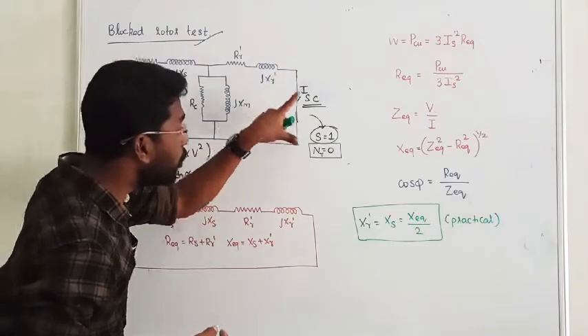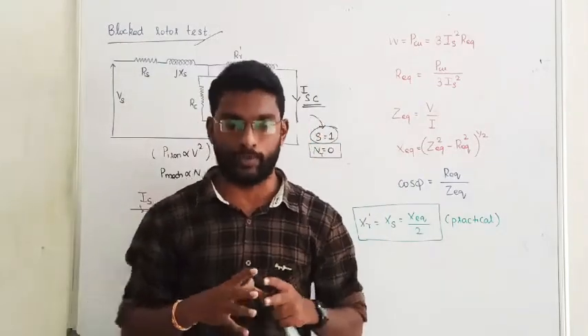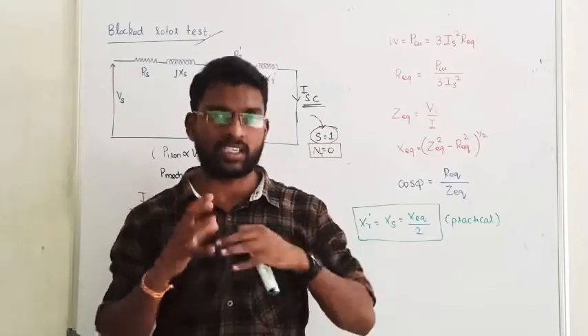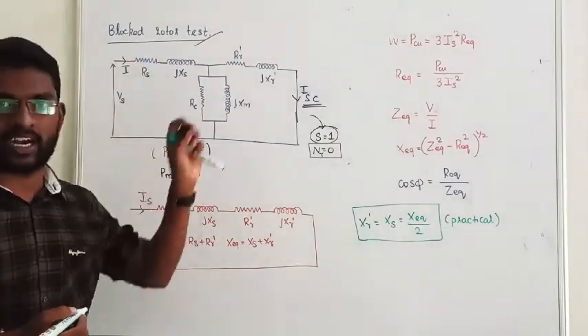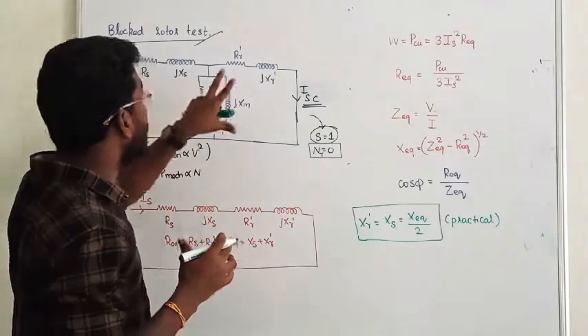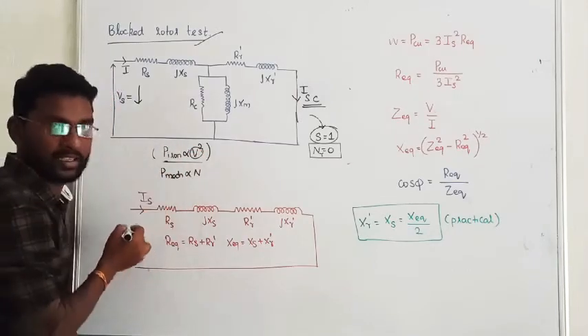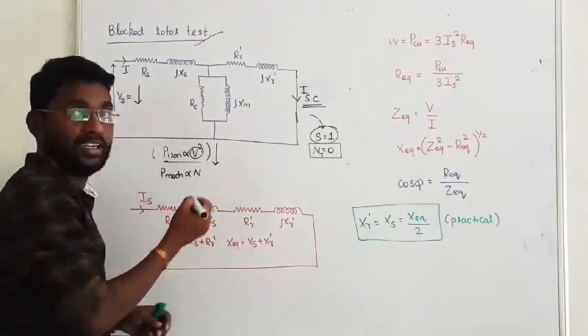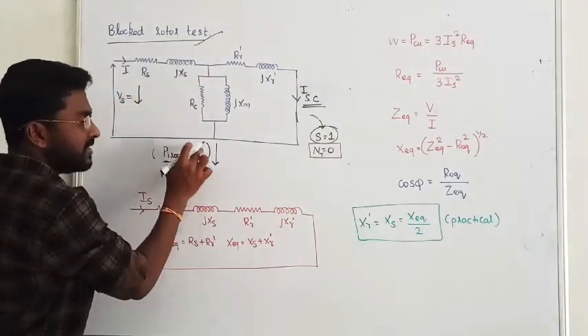This test is called short circuit test or blocked rotor test. Open circuit test, that is no load test, we applied rated voltage but the amount of current is very very less. In short circuit test, current is very very high, almost rated current, but the applied voltage will be reduced, that is very less amount of voltage.